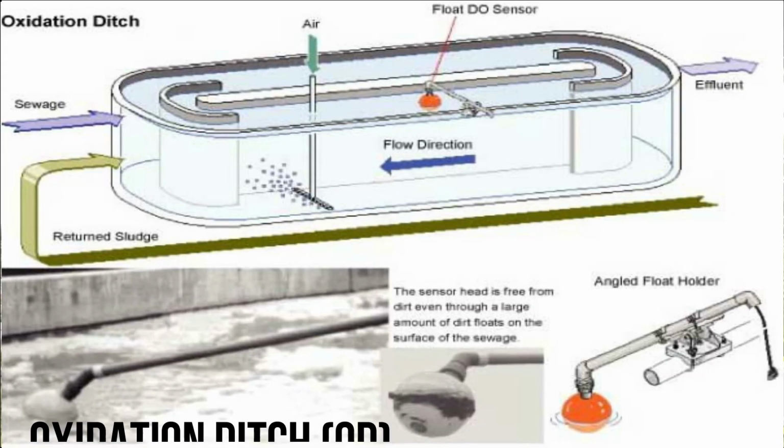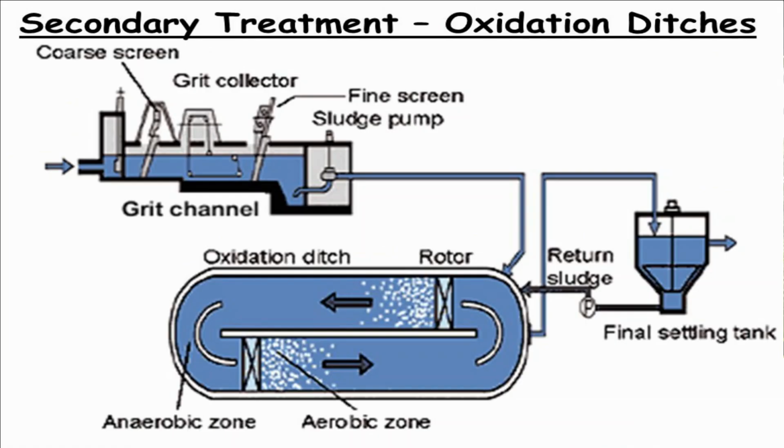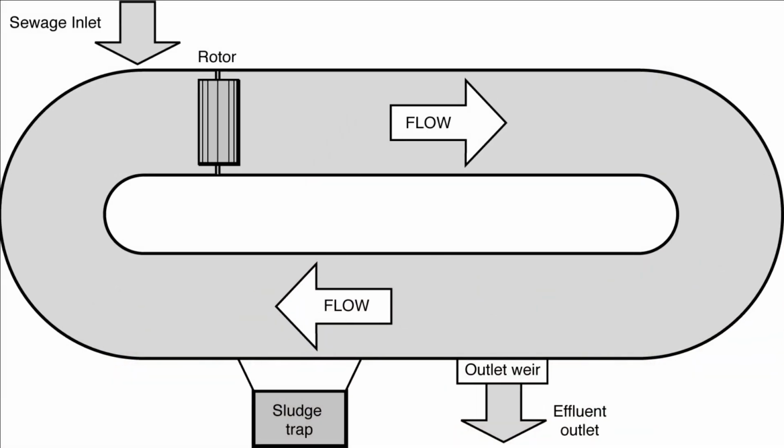Over the last 20 years, a variety of methods of wastewater treatment systems have been developed in order to improve effluent quality. Oxidation Ditch, or OD system, which is a mechanized secondary treatment, is a modified form of the activated sludge extended aeration system that utilizes long solids retention times (SRTs) to remove biodegradable organics. This system can be easily adjusted to meet most combinations of incoming sewage and effluent standards and has achieved both biochemical oxygen demand (BOD) reduction and nutrient removal.